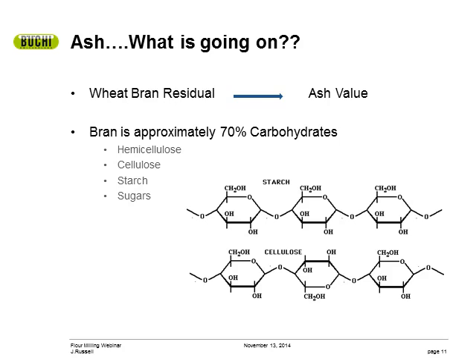Before flour millers implemented full-spectrum technology, back in the 80s, you were looking at the color of the flour, relating the color back to bran concentration, and then relating that to ash — essentially a tertiary correlation that did not produce a very linear response. That is why back then you would need separate biases for spring wheat, winter wheat, soft wheat, and sometimes even different mills — A mill, B mill, C mill. But with modern spectrometers, the ash concentrations are beautifully linear and with a high level of accuracy. Still, it is important to understand that ash is an indirect measurement when using NIR spectroscopy.